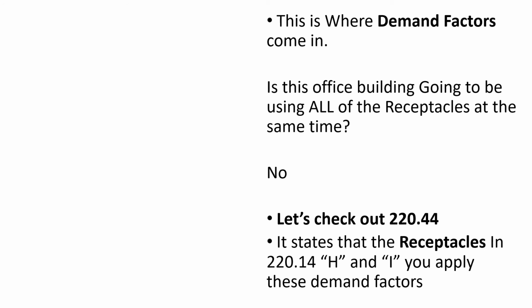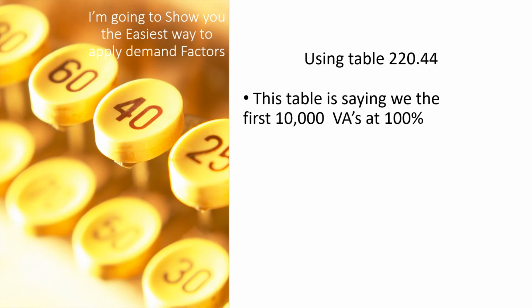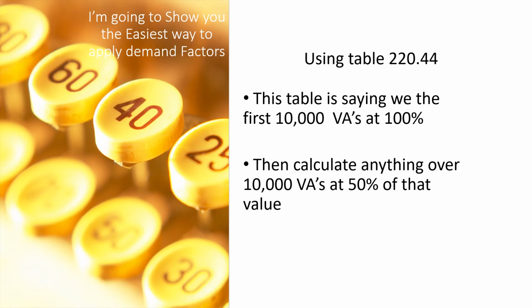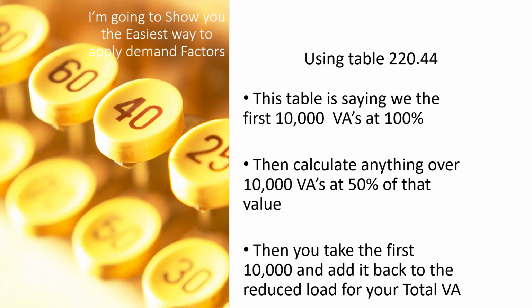220.14(K) for banks and offices told us that we must calculate it according to (I), which allows us to use this code article and these demand factors. We're going to learn how to do that now, using Table 220.44. I'm going to show you the easiest way to apply demand factors no matter what. The table says we must do the first 10,000 VAs at 100%. Then we calculate anything over 10,000 VAs at 50% of its value. Then you take the first 10,000 and add it back to the reduced load for your total VAs. I'm going to teach you the easiest way to do that now.